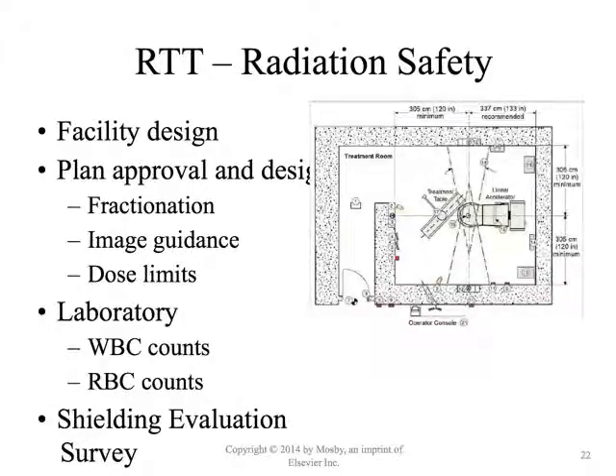So for radiation therapy safety, again, facility design is probably the number one thing that we are looking to for ways to protect personnel from this stuff. And what that looks like for the linear accelerator is a treatment vault, right? So we're going to have a corner here that has reinforced concrete, as well as a door, like a 2-ton lead door that opens and closes very slowly, because we don't want the radiation to scatter and exit the treatment area, right?